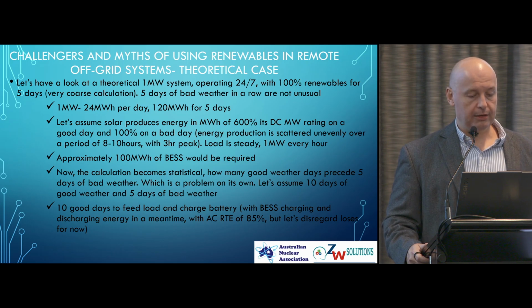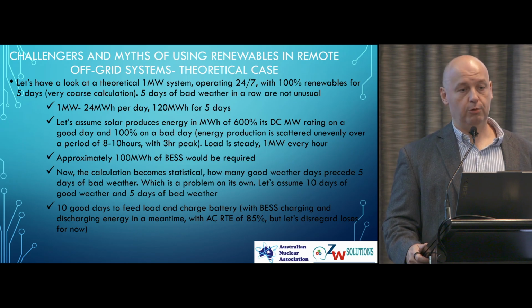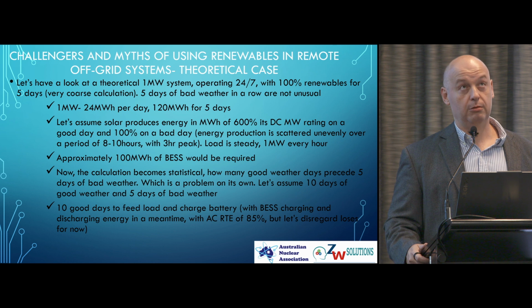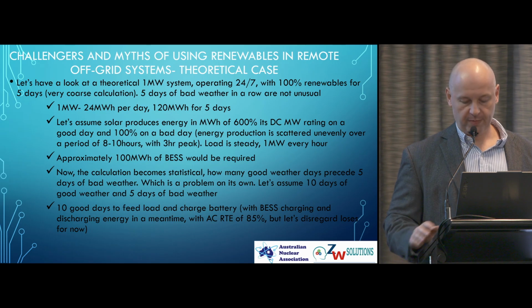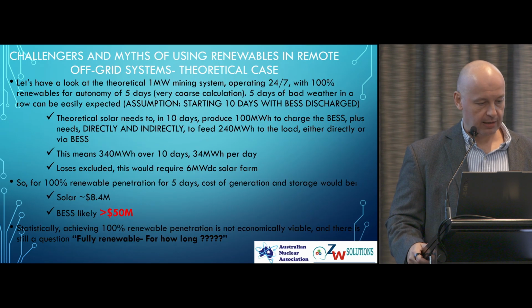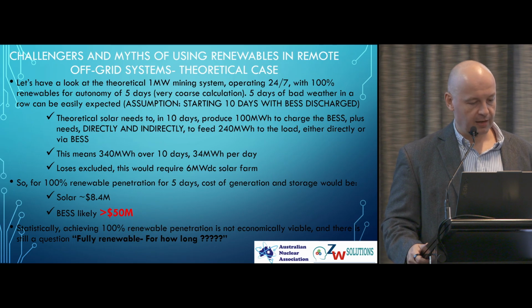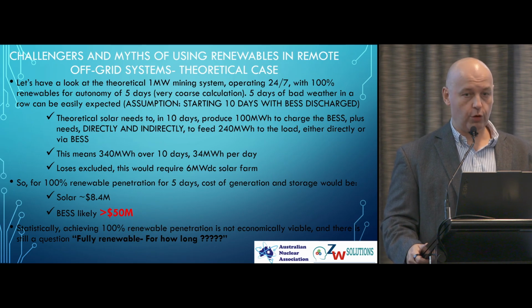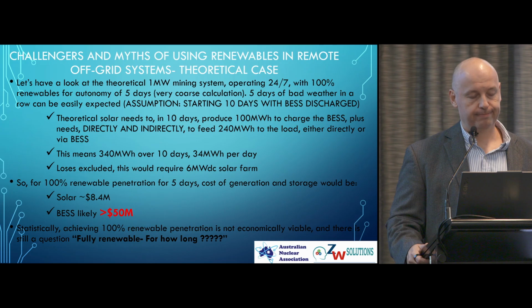So in order to supply a 1 megawatt system for 5 days of bad weather, we would need roughly 100 megawatt hours of batteries. 100 megawatt hours. That's about 12, 13, 40-foot containers worth of batteries. So the next one, let's look at the price. For 2 hours, it was costing 11 million per megawatt of load.